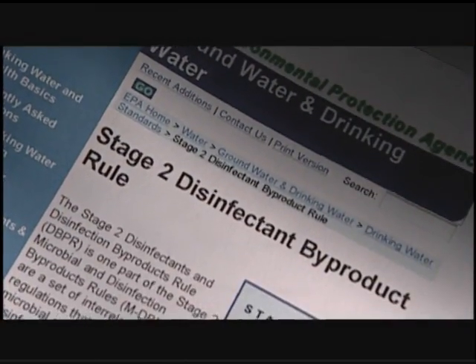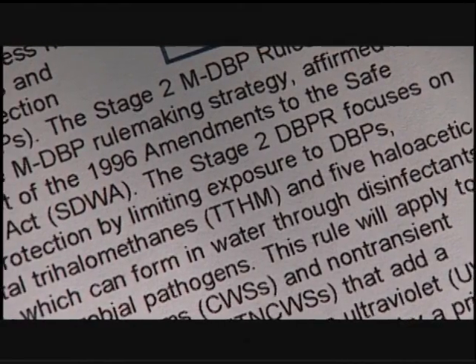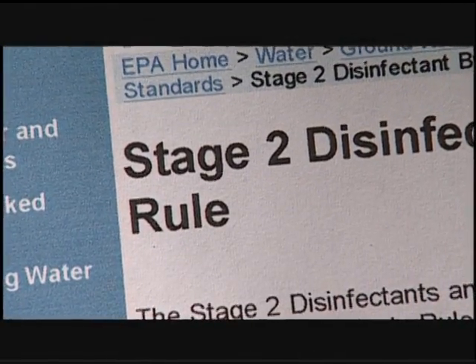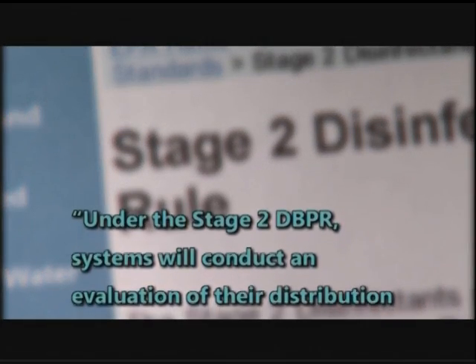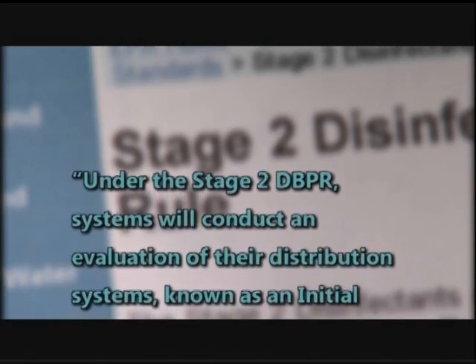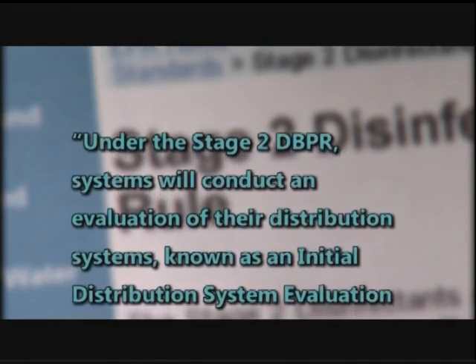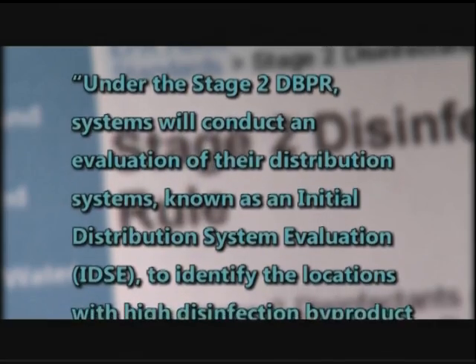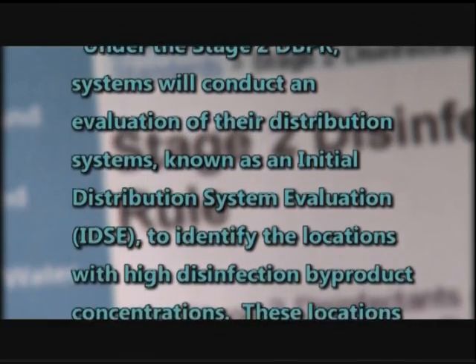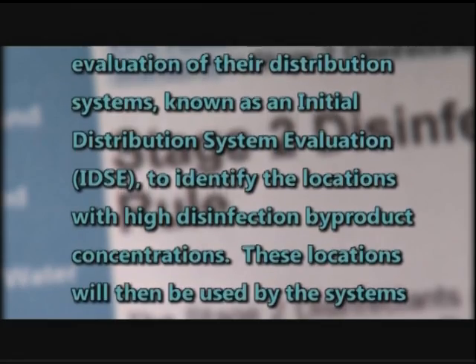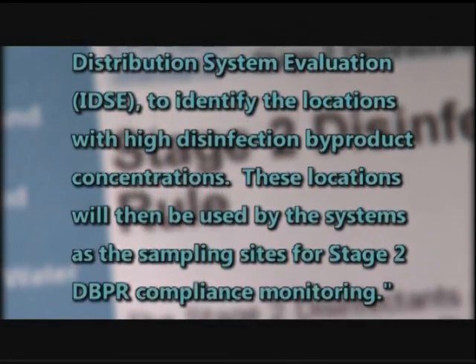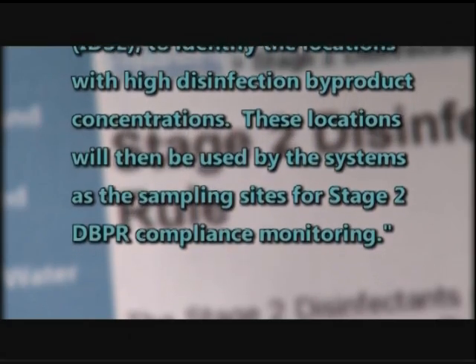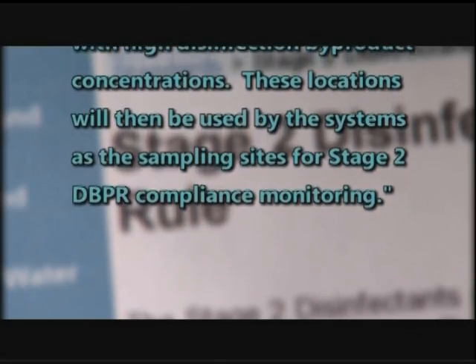The Stage 2 Rule, put in place in 2006, builds upon the earlier rule and works to provide additional public health protection from DBPs. According to the EPA, under the Stage 2 DBPR, systems will conduct an evaluation of their distribution systems, known as an Initial Distribution System Evaluation, to identify the locations with high disinfection byproduct concentrations. These locations will then be used by the systems as the sampling sites for Stage 2 DBPR compliance monitoring.